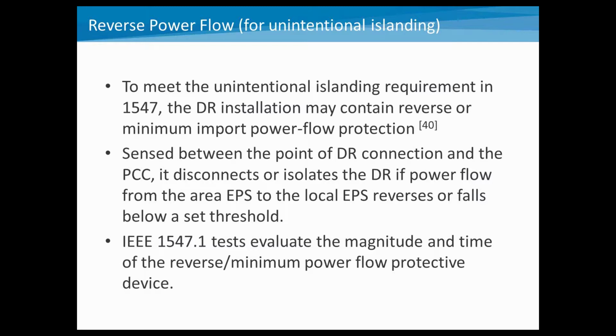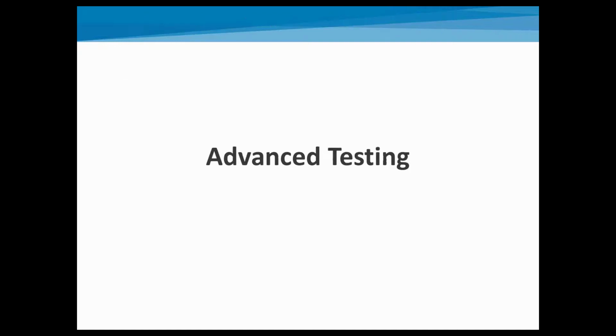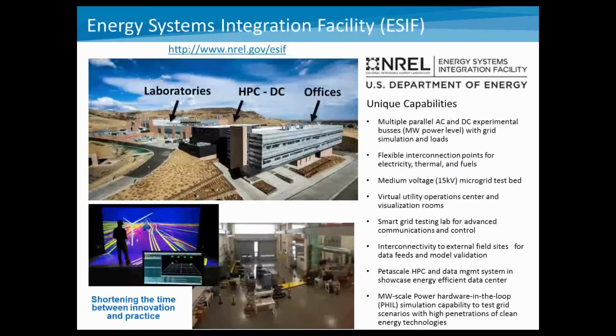Again, these are the standardized tests in 1547, developed over a number of years and used successfully for quite a few years. And those are also integrated into UL 1741 for actual certification processes. Again, the big thing to realize is that that's on a single distributed generator, and some of the challenges we have when running those tests is the ability to match real and reactive power extremely precisely. Even in the testing laboratory, it takes a lot of work to get that very precise and cause these island conditions. And the other thing, like I mentioned before, is that it is only done on one inverter. So what I'm going to cover next is advanced testing to resolve some of the issues that I just brought up.